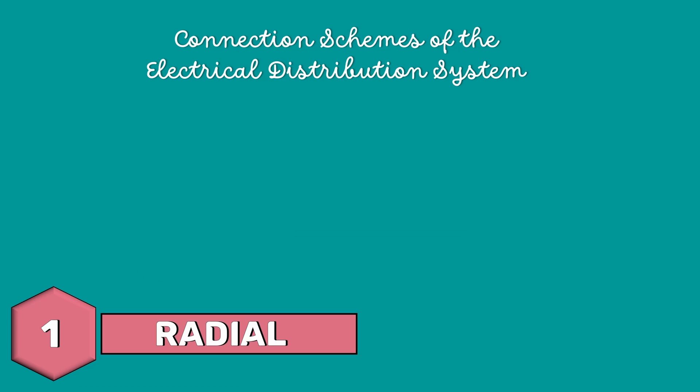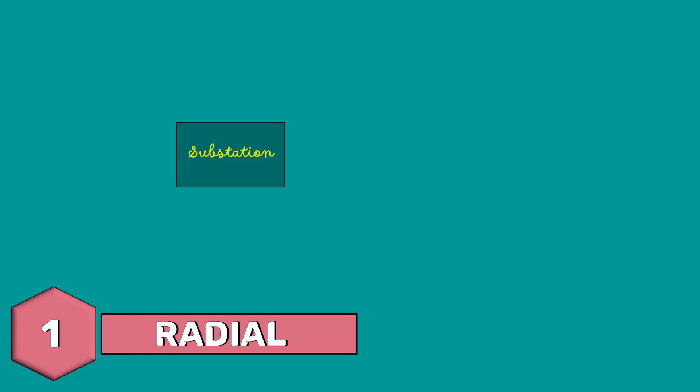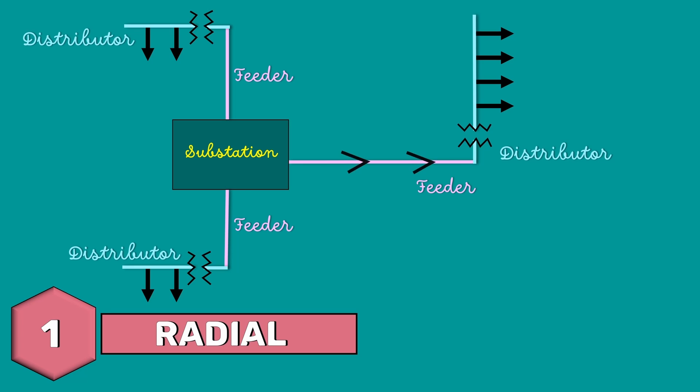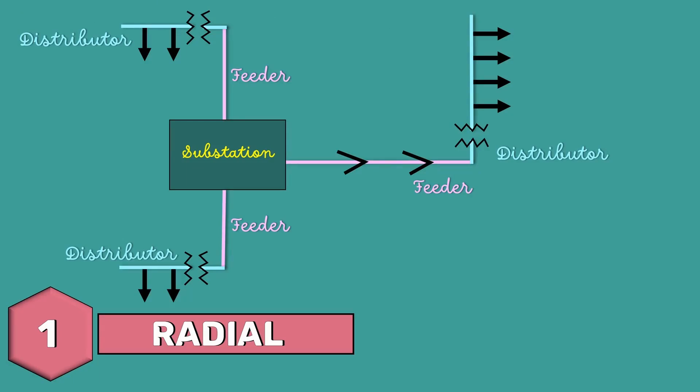Let's first start with the radial system. Here, separate feeders radiate from a single substation and feed the distributors at one end only. This is the simplest and cheapest network for an electrical grid. This radial system is employed only when the power is generated at very low voltage and the substation is located at the center of the load. This serves light and medium density load areas.